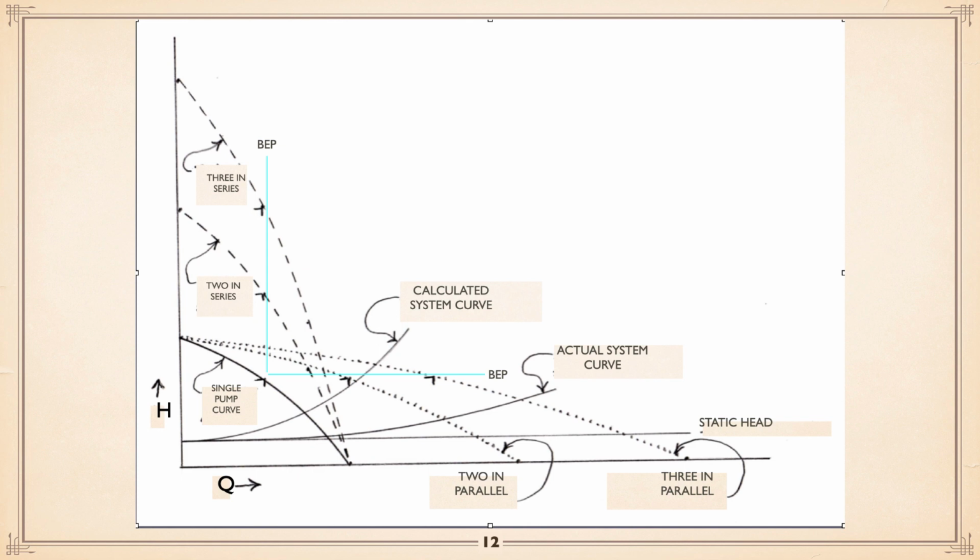is much flatter. There isn't that much friction there. So one pump, you're way off to the right. Two, you're still the wrong way. Maybe only when you get three and the flow rates are high are you getting something reasonable.